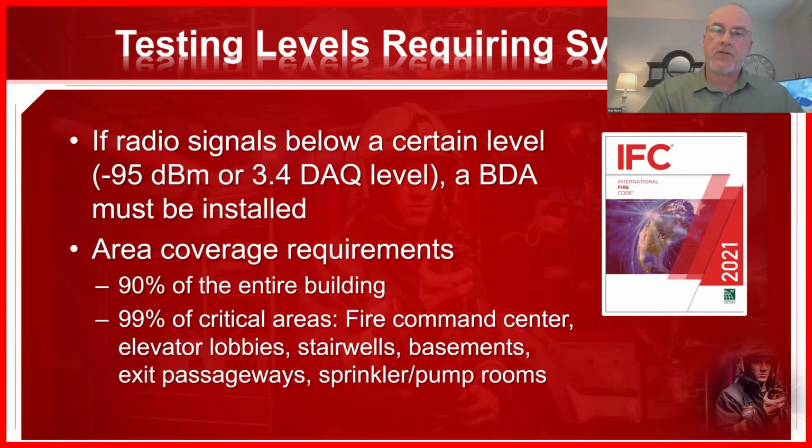The critical areas are things like the fire command center, elevator lobbies, stairwells, basements, exit passageways, and sprinkler or pump rooms. Those are like, hey, we got to have coverage in virtually every corner of those critical areas, but we don't necessarily have to have it for every single inch of the building.